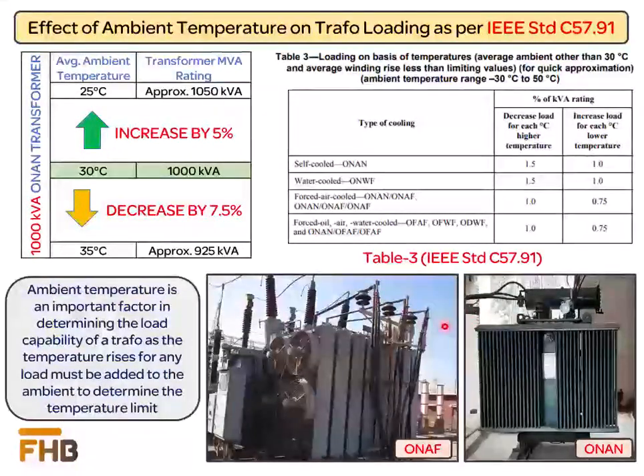For quick approximation, IEEE standard C57.91 under table 3 provides an ambient temperature based criteria according to which we can increase or decrease the loading of the transformer. According to the approximation, if the ambient temperature is lower than the designed ambient temperature of the transformer, then the kVA rating of the transformer will increase by the values shown here. And if the ambient temperature is more than the designed ambient temperature, then the kVA rating will be decreased by the values shown here. We have considered a 1000 kVA transformer which is designed at 30 degrees centigrade ambient temperature. Here we can see that with the increase or decrease of the ambient temperature, the kVA rating of the transformer varies from the designed kVA rating.